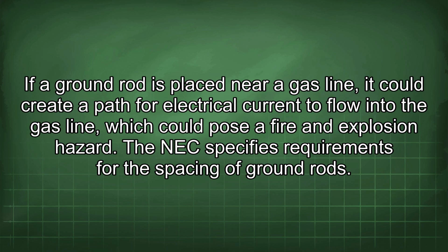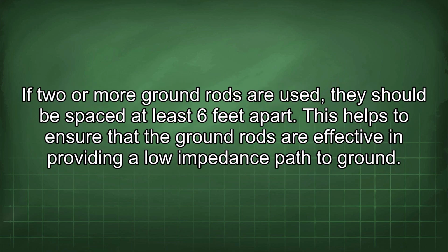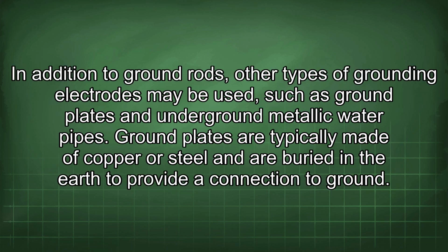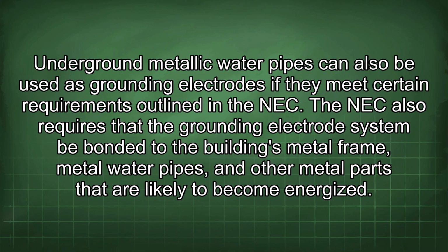The NEC specifies requirements for the spacing of ground rods. If 2 or more ground rods are used, they should be spaced at least 6 feet apart. This helps to ensure that the ground rods are effective in providing a low impedance path to ground. In addition to ground rods, other types of grounding electrodes may be used, such as ground plates and underground metallic water pipes. Ground plates are typically made of copper or steel and are buried in the earth to provide a connection to ground.